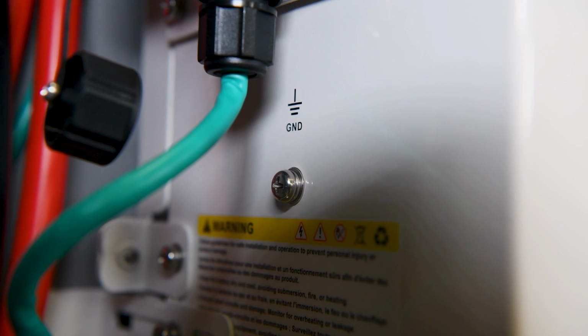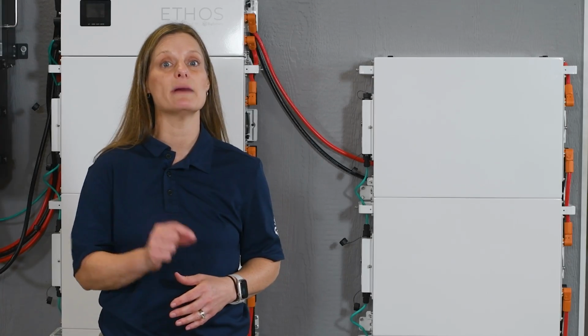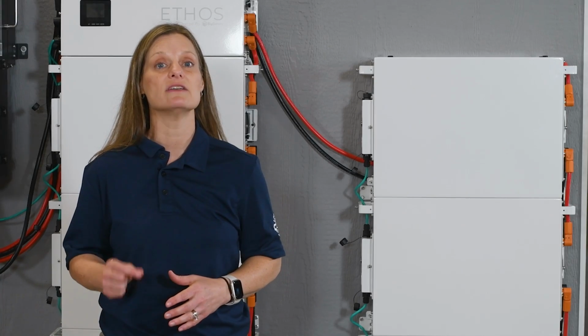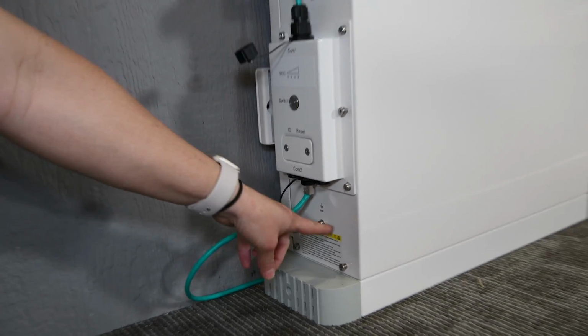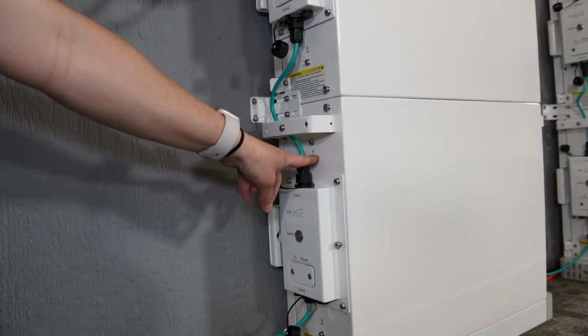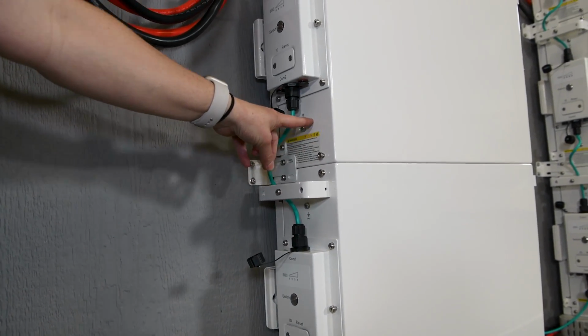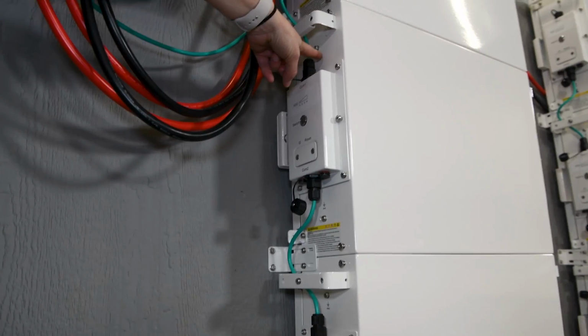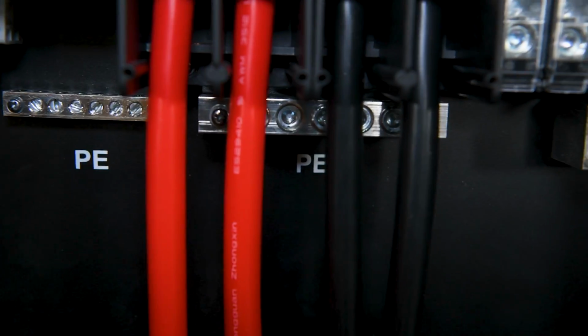If you decide to ground your system, it's advised to use an electrical grounding conductor to link the battery modules together by connecting from one grounding screw to another in a daisy chain fashion, much like the rest of the cabling, passing through the controller box and ultimately attaching from the controller box to the protective earth bus bar in the inverter. This method is a proactive step towards ensuring your system's safety.